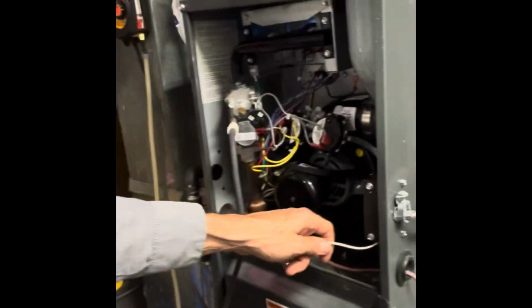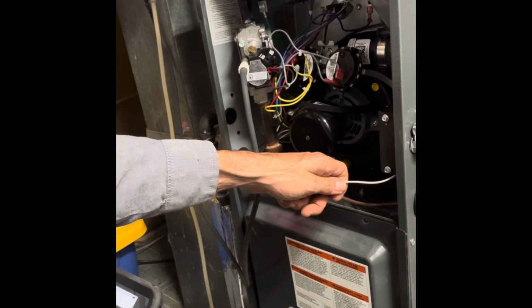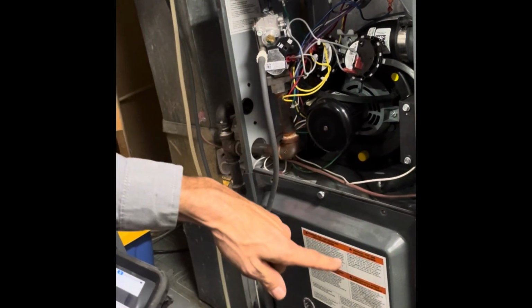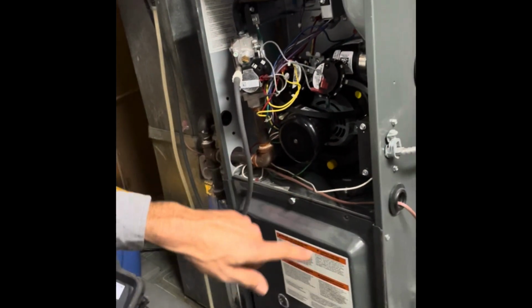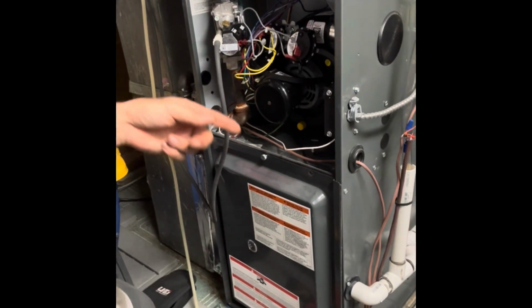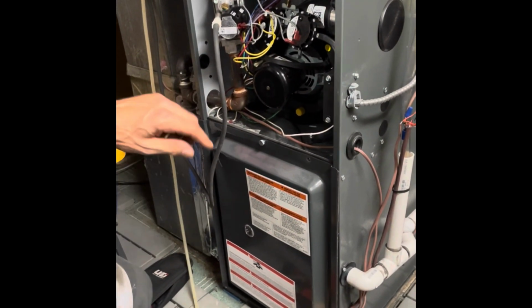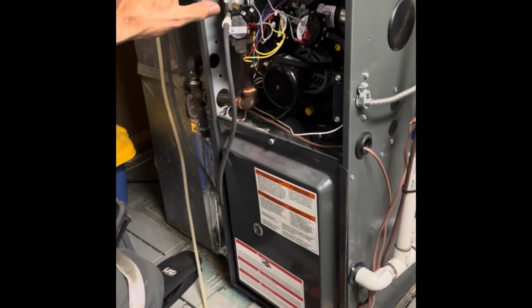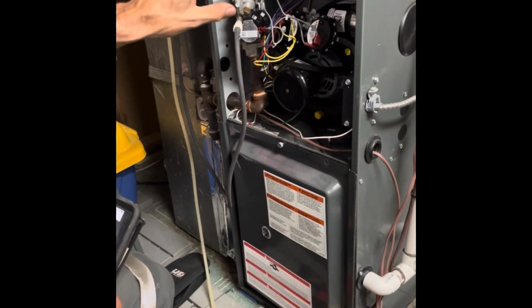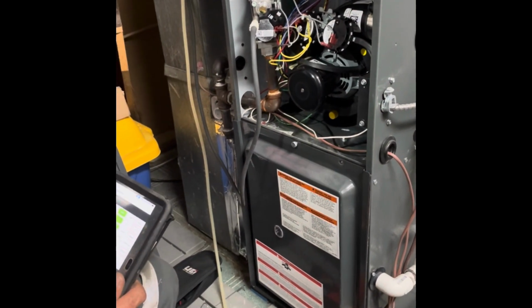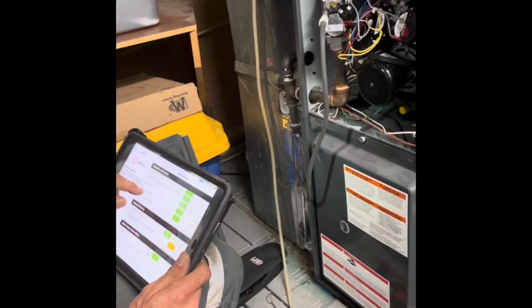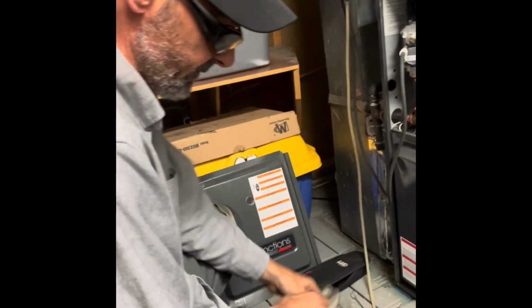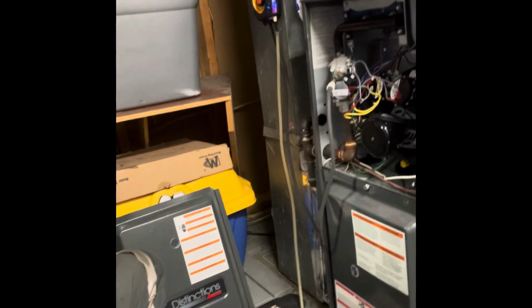On a 2-stage furnace, if I'm in low heat mode and I look at my meter, I'm lucky to hit a 2. That's with our venter going and our blower. The blower runs a lot slower in low heat mode, which is why it uses less power. When we get a high heat only furnace, it creates a lot of heat, so that fan has to run a lot quicker than a low heat mode furnace. I'm going to stop operation of this furnace by taking that door off.